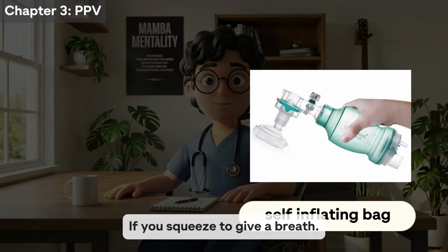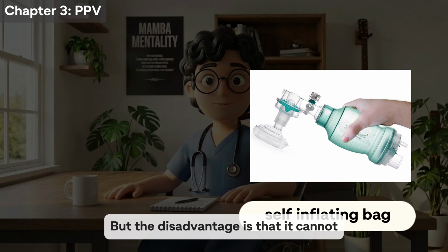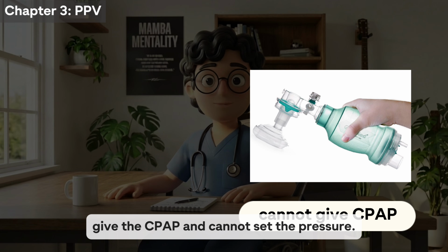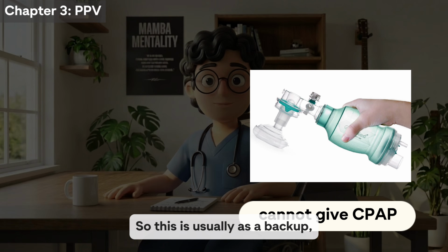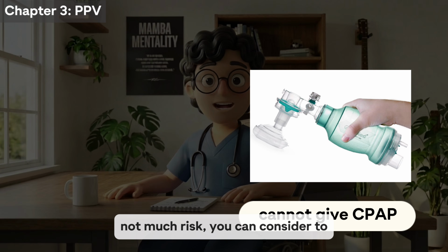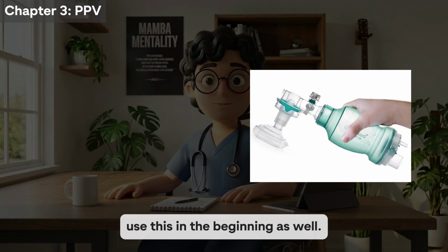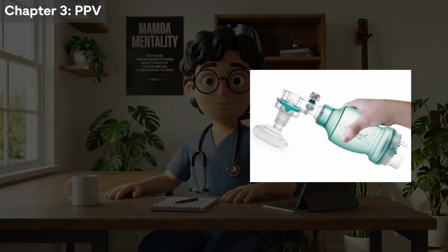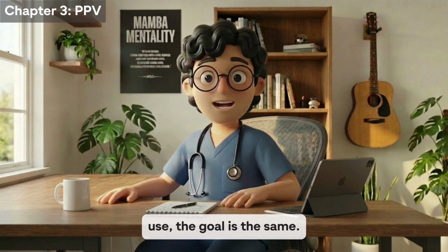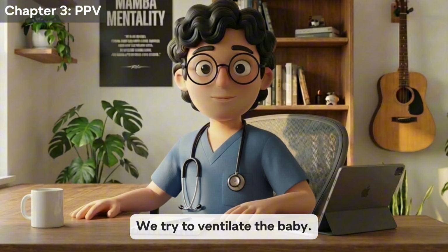On the right is a self-inflating bag. You squeeze to give a breath, but the disadvantage is that it cannot give the CPAP and cannot set the pressure. So this is usually a backup, or if you think the baby is term with not much risk, you can consider using this in the beginning as well. Whichever device you use, the goal is the same. We try to ventilate the baby.